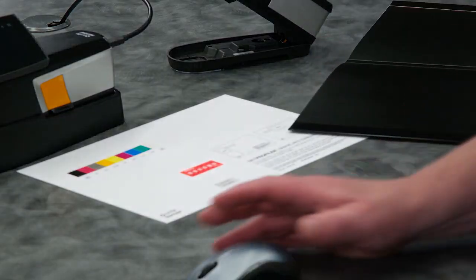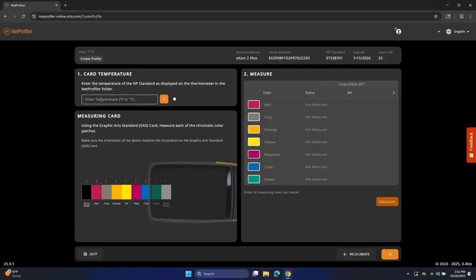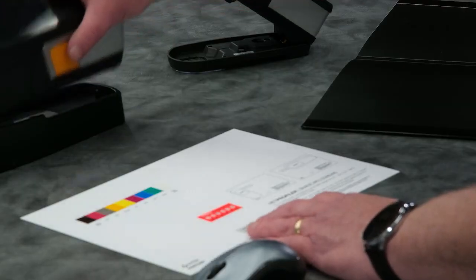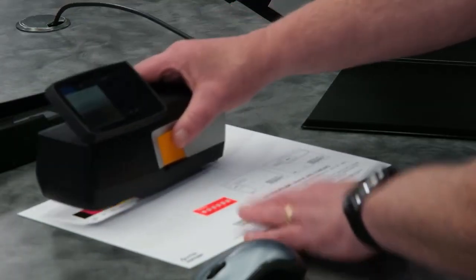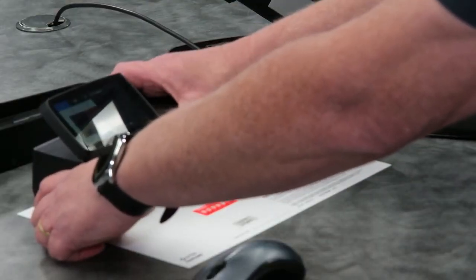And so this one right now says it's 70. So I'm going to type in 70, hit the checkbox. I've got an edit button if I made a mistake and need to retype it. But now that that temperature is in, I can go ahead and take these measurements. And it tells me order of measuring does not matter.